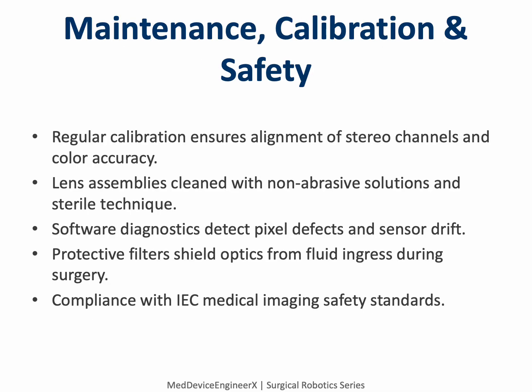To keep image fidelity high, Hugo's vision components undergo routine calibration. Stereo alignment is checked to maintain true depth rendering, while color balance is verified against reference charts. Optical surfaces are cleaned using approved non-abrasive agents, and the endoscopic channels are sterilized between every case. Internal diagnostics monitor sensor drift, dead pixels, or overheating, alerting service teams before any issue affects performance.